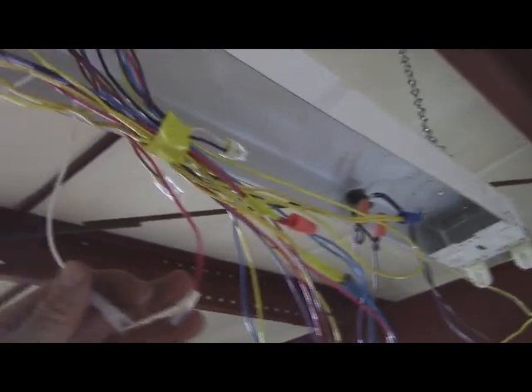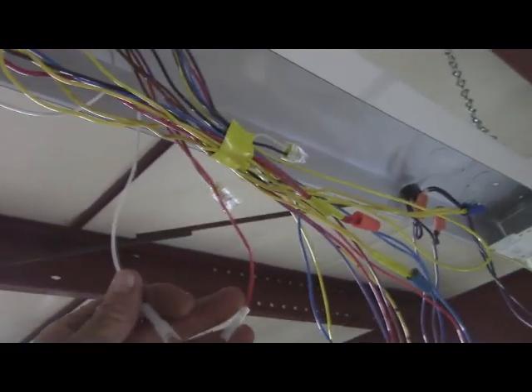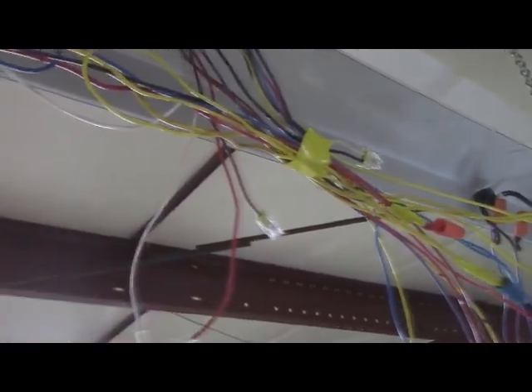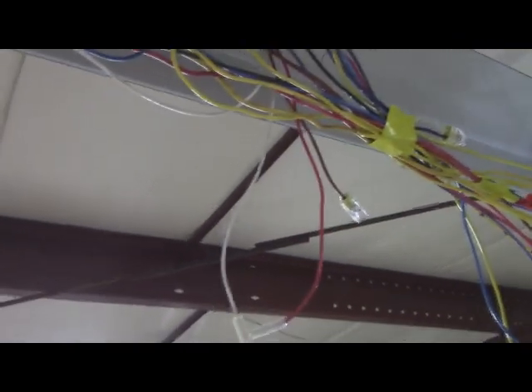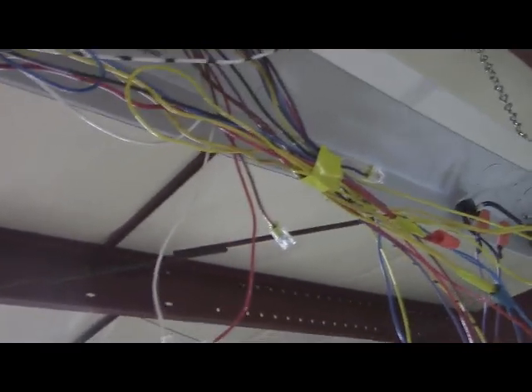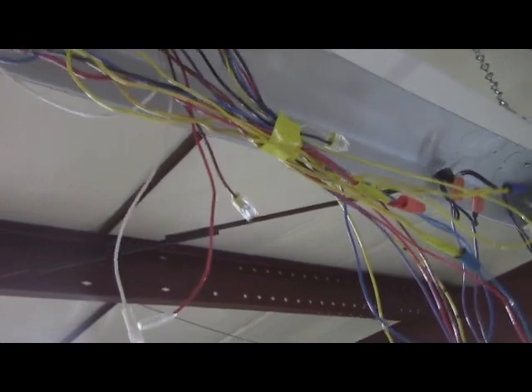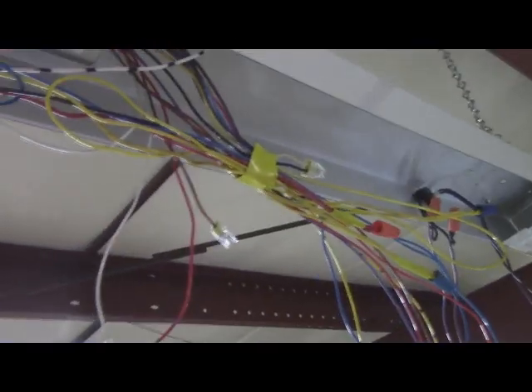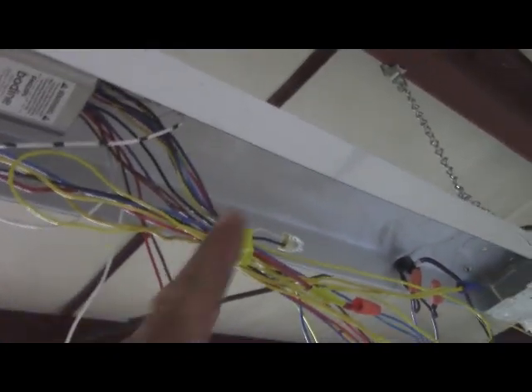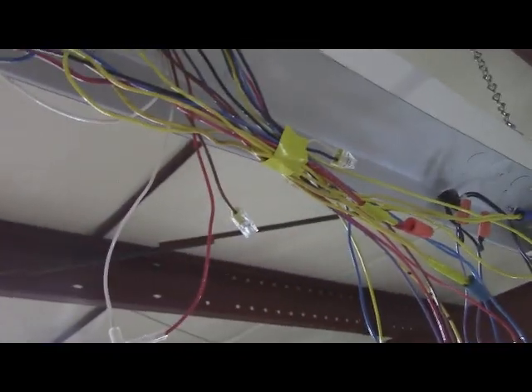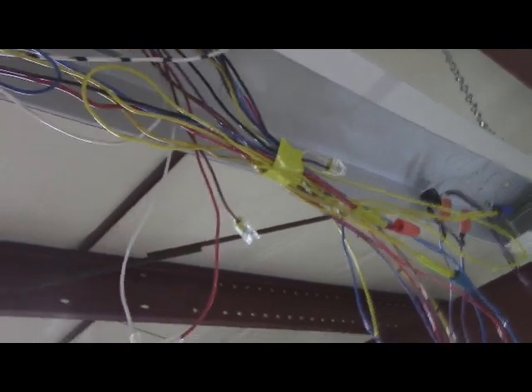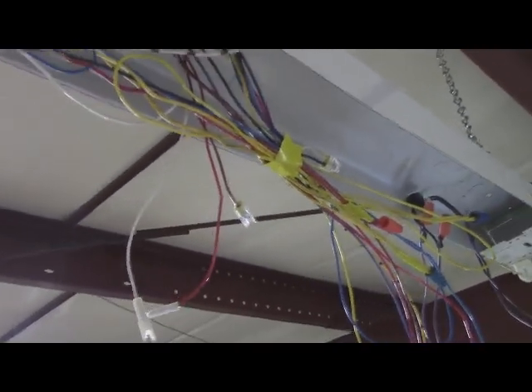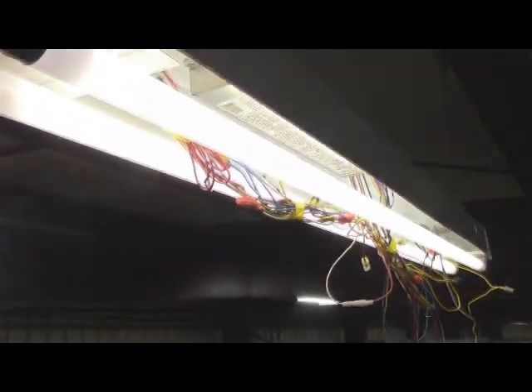in these 2 locations, they should light up before I turn AC power on. I just want to see if the battery pack is in good order and that the emergency ballast is working in emergency conditions. And then if that works, then I'll plug in AC power. And I have it wired for these 2 locations here. So hopefully, if the wiring's correct and I plug that in, I'll put 2 tubes in there and see what happens. Okay, very good. So our 2 tubes are lighting up pretty brightly.